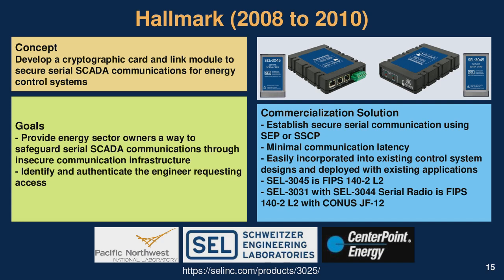The first SEDS project SEL was involved with is called Hallmark, started in 2008 with Pacific Northwest National Labs and Centerpoint Energy. The goal was to develop a cryptographic method to secure serial SCADA communication for energy control systems, regardless of the WAN infrastructure the serial information is tunneled through. This resulted in several SEL products, including the SEL-3045 serial encryptor and the SEL-3031 serial radio — both with FIPS 140-2 level encryption cards, and the radio with JF-12 CONUS approval. The seeding randomization in the encryptor card is currently being updated, and we expect FIPS 140-2 validation completed by end of year.